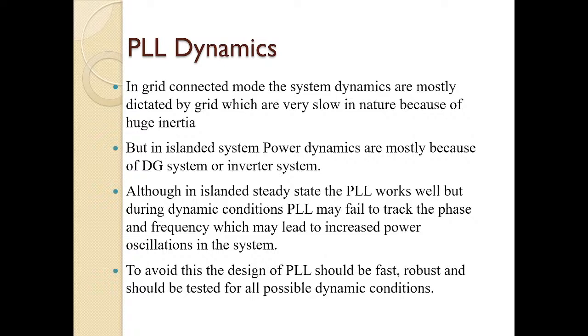So as PLL is basically an equation, it has mathematics in between. The mathematical stability of the PLL is very important. That means when there is a change in the voltage magnitude and the frequency of the grid, the PLL may differ in its performance. So based on what mathematics you are putting and how the mathematics has been written, the dynamics of the PLL will vary. That means the rise time, settling time, and many things will vary. And because of this variation, there will be issues in the stability conditions, and the inverter will enter into an unstable situation, maybe if the PLL mathematics is not properly written and analyzed. Hence, in a grid connected mode of operation, the PLL dynamics is very, very important.